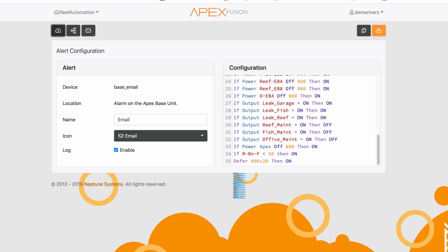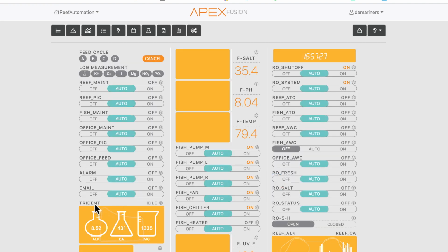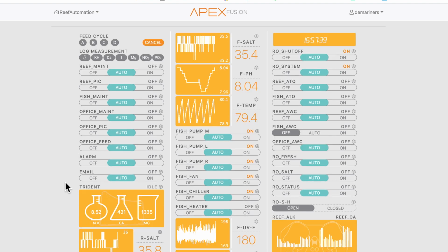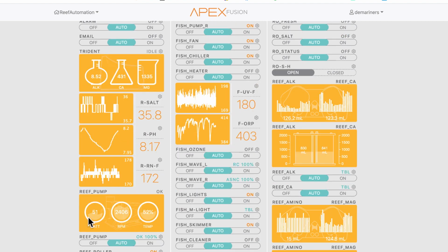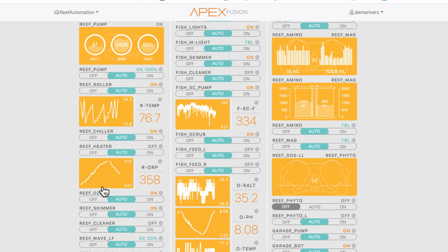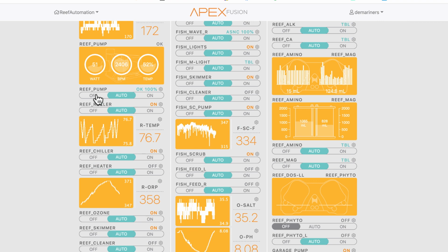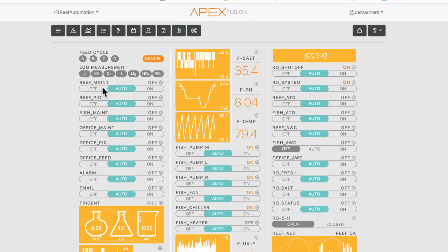There's a lot of other things you can do with this flow. Now, for instance, I have a couple things set up that if I turn on my maintenance, what's going to happen is my pump's going to turn off, and therefore my flow is going to register 0. So what I want to be able to do is know if my reef pump is less than 0 at any time other than when it's on maintenance, because once I turn maintenance on, it's going to alert me, and I don't want to get alerted if reef maintenance is on.